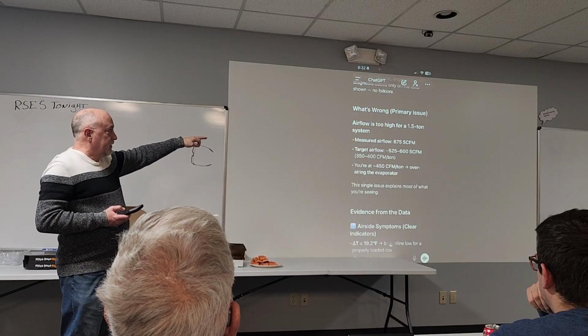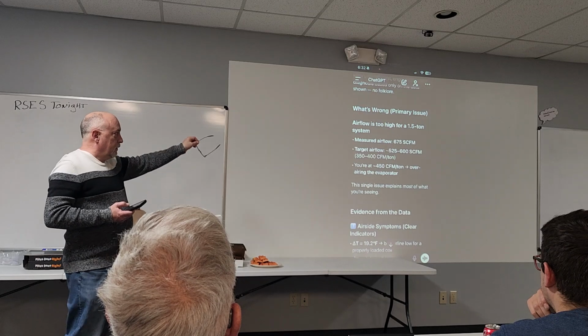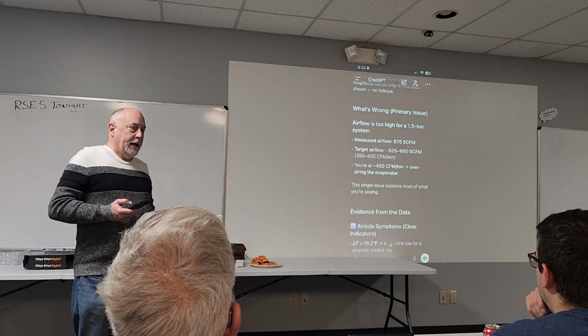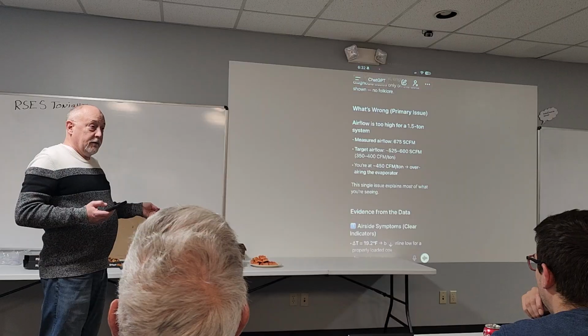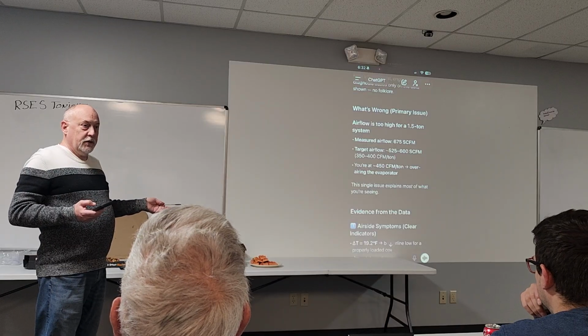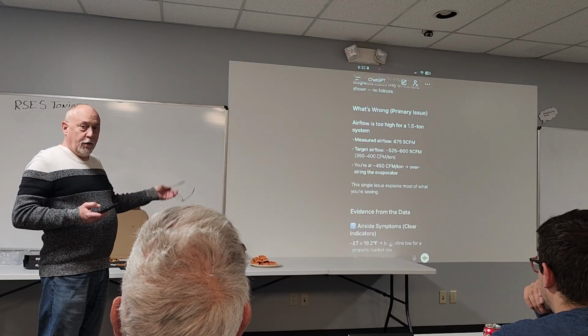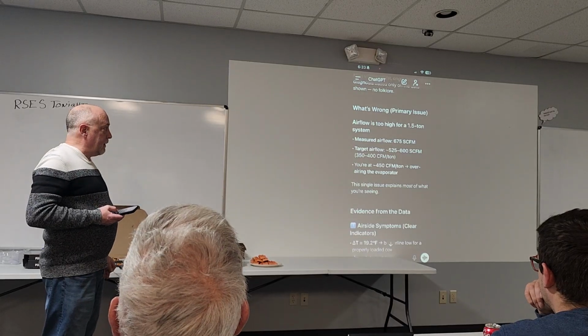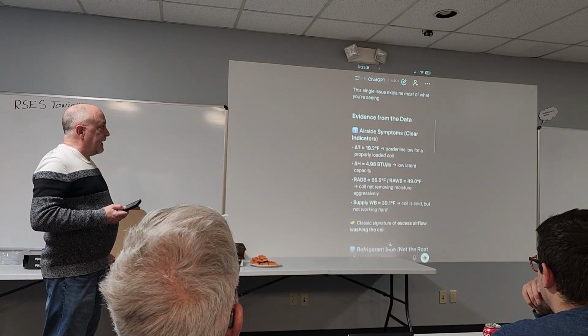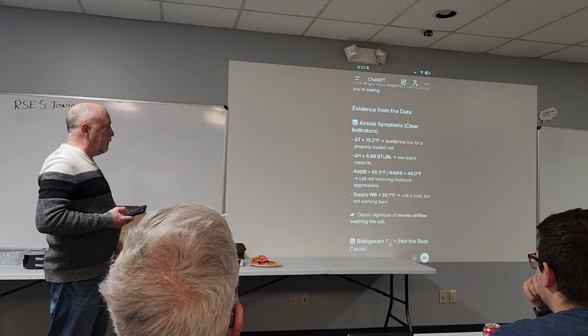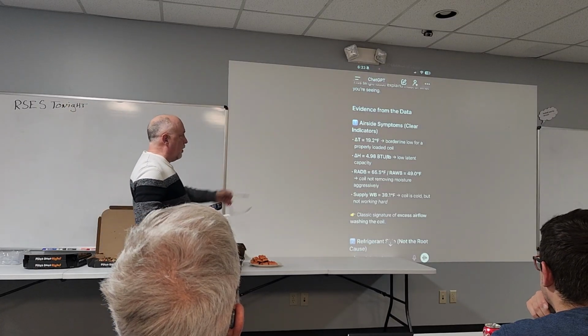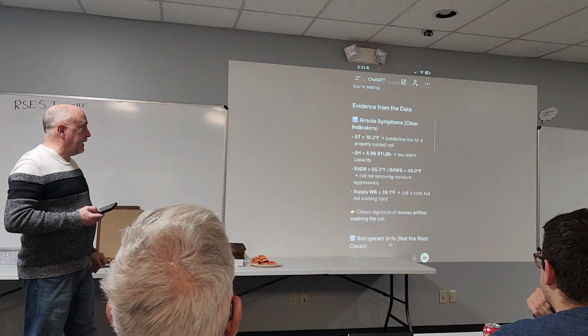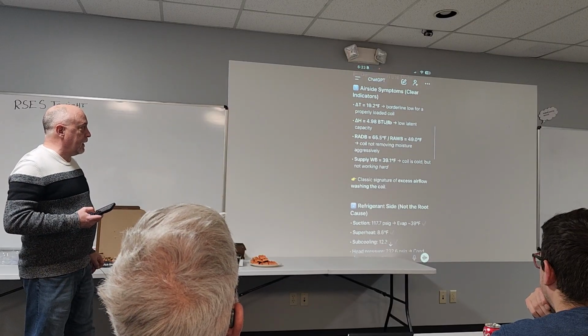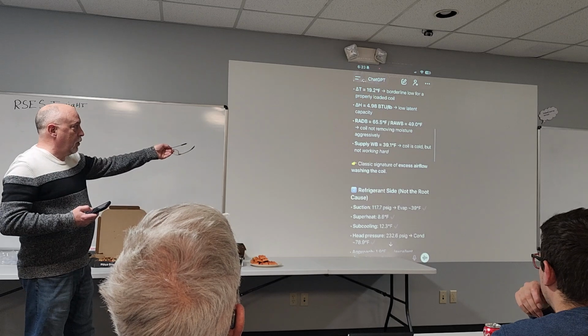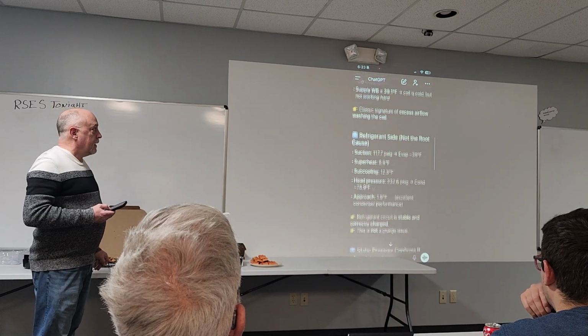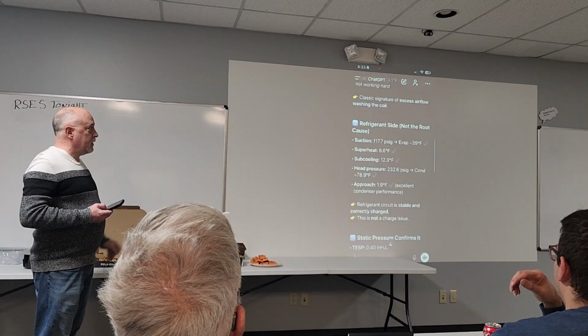Airflow is too high for a 1.5 ton system, measures 675, so it's looking for about 400 CFM per ton. Now I can do things like pick up where our geolocation is, so it can say, okay, you're in a mixed climate in Ohio, so 400 CFM per ton. If you were in Arizona, you would be at 450. If you were in Florida, you might be at 350. Your airside indicators of 19 degree splits are borderline for a properly loaded coil. Low latent capacity, there you go, Phil. Phil got the latent capacity right. The coil's not removing moisture aggressively. Supply wet bulb is 39.1, that's cold, but it's not working hard. Classic signature of excess airflow washing the coil.